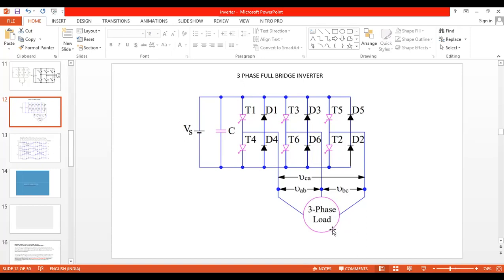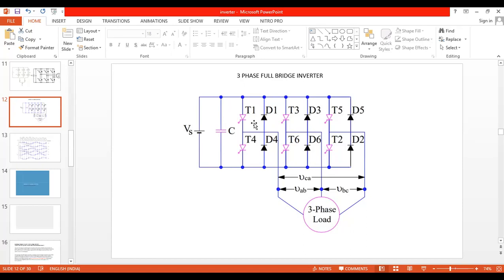We need to turn on the induction motor using the inverter when the supply is DC. Looking at the circuit, a capacitor is placed in parallel with the source if the source does not provide a pure constant DC voltage. This is called a voltage source inverter. The capacitor gets charged and provides constant voltage to the inverter circuit. This is also called a six-pulse inverter because we use six SCRs.